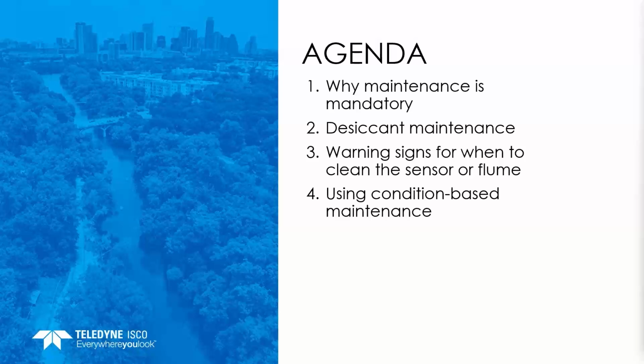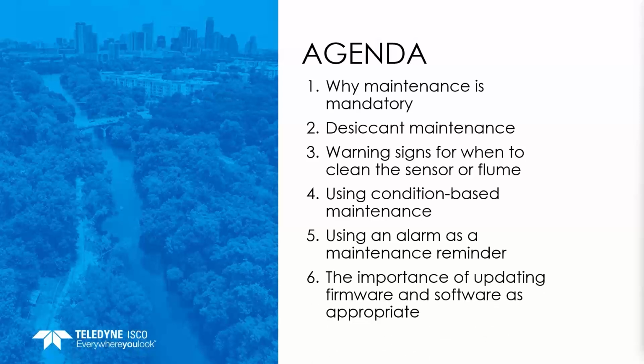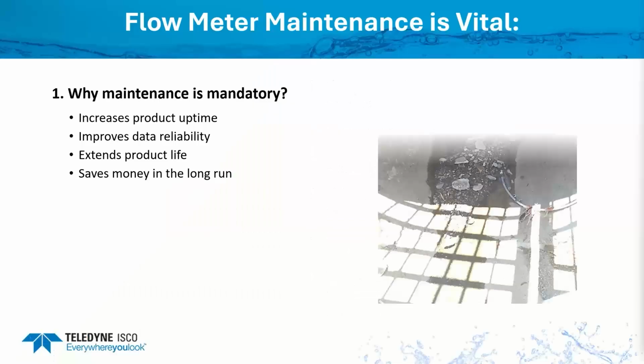Then, condition-based maintenance: using the tools that you have available, for your level, temperature, signal strength, and any diagnostics, as a means to determine when to do maintenance instead of just a standard operating procedure, going out there every 2 months just because the calendar says you should. Last, we're going to cover using an alarm as a maintenance reminder. We'll also cover the importance of updating firmware and software, and I'll give you some tips on that at the end of this presentation.